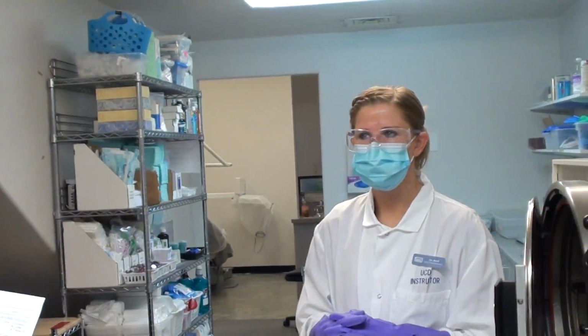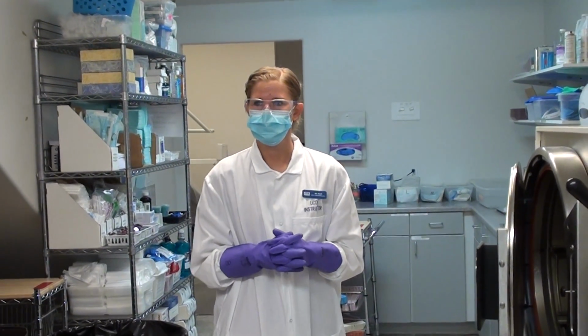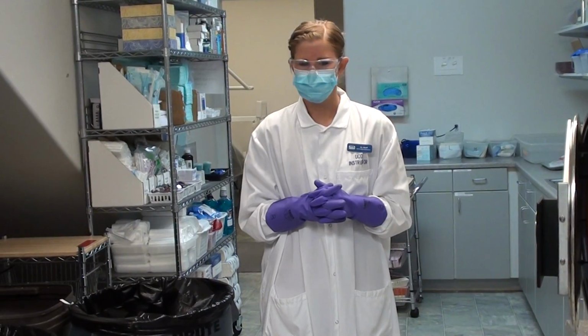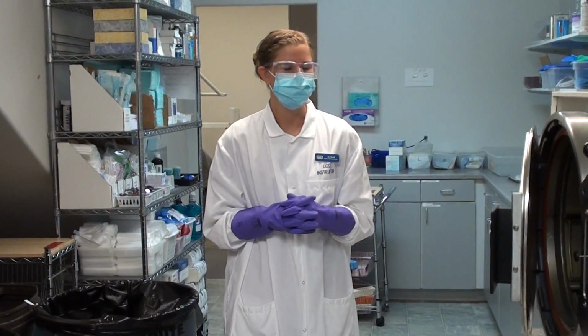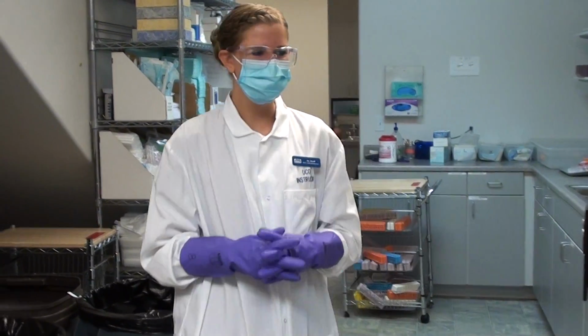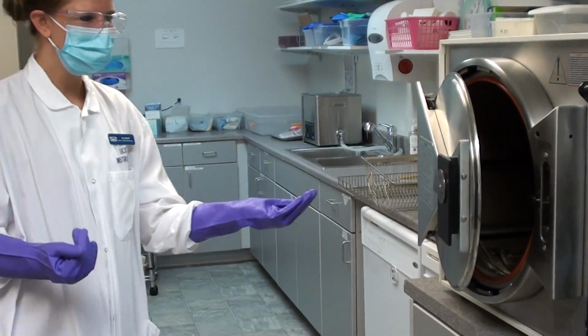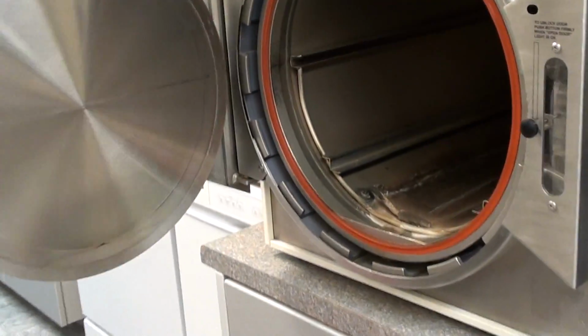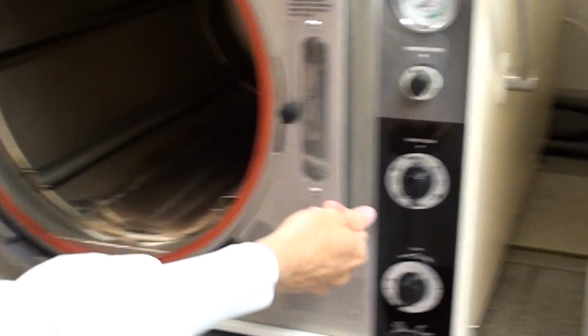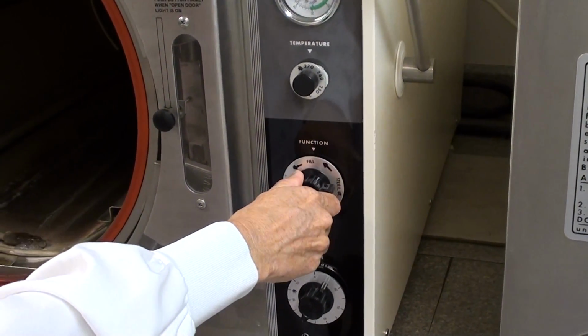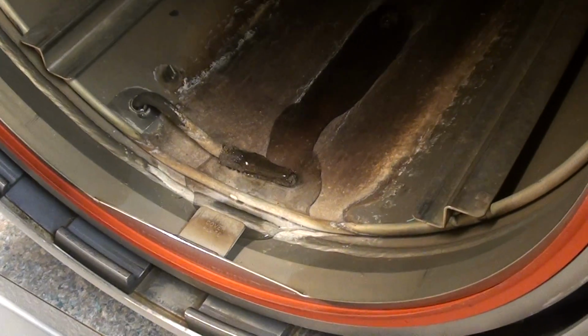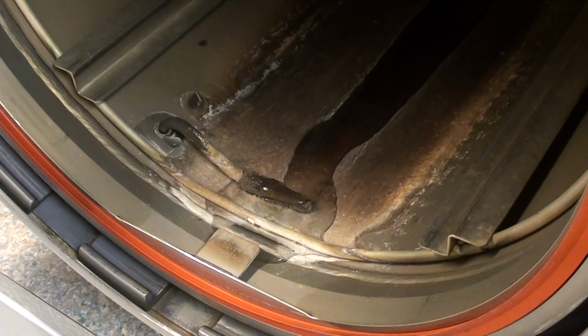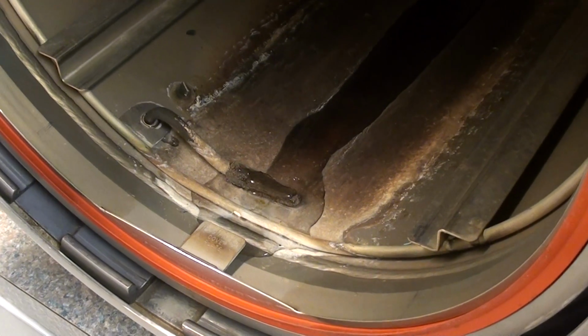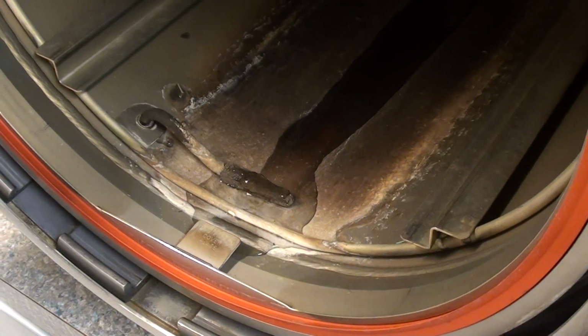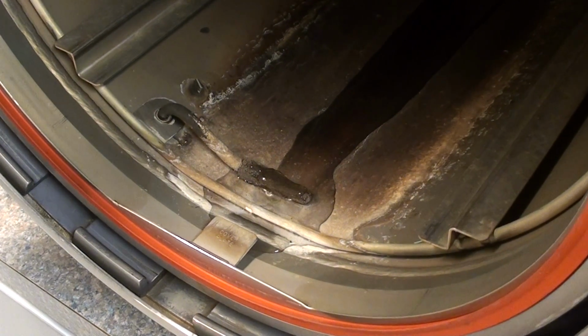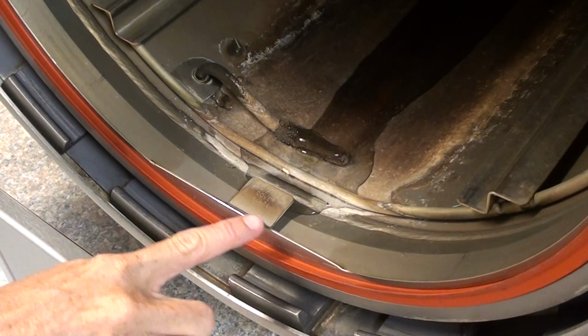Okay, now that she's checked the fill levels, she's going to turn the control knob to fill and watch the chamber to be certain enough distilled water is dispensed but does not overflow. So once again, I'm going to ask my friend because all of this is clean. Kelly, can you open this door for me? I would love to. Can you turn it to fill? And because you're the one who turned it to fill, do not leave. I'm not allowed to leave now. So we're going to watch this so you can see it doesn't take long to fill up. You don't go anywhere until it's all the way done. What we're watching for is this plate. We want the water to cover it. It even says cover plate.